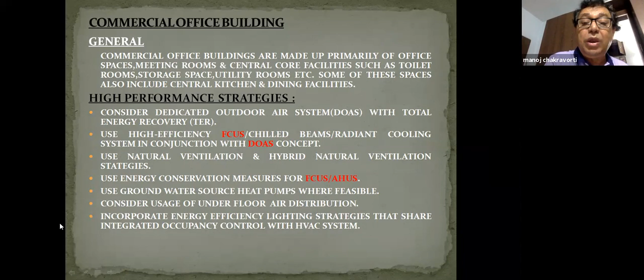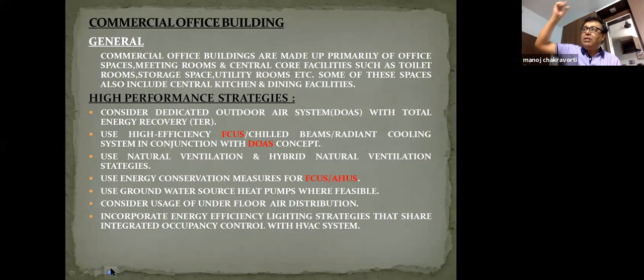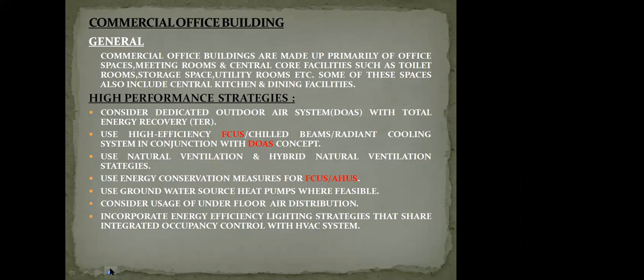Supposing we go for a radiant cooling system for Calcutta, it is very difficult, because in Calcutta there is high humidity. In a radiant cooling system we can save energy. We can take the chilled water pipes either at the roof or at the floor level. If we take it at the floor level, then I will have to keep the floor surface temperature above the dew point temperature. If it is less than the dew point temperature, then what will happen? We will have to induce fresh air, and when fresh air is induced, if it is humid and too much moisture is there, then automatically condensation will be the result.